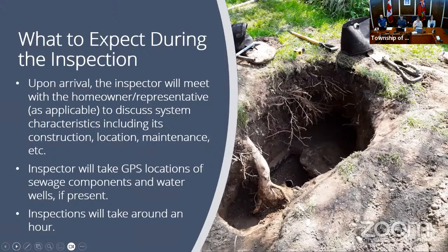We would also ask questions like maintenance. So when was that last pump out? Do you have that receipt? And then what is your typical pump out frequency? So just for us to know that you pumped it out 6 months ago doesn't necessarily help us or help you in our conversations to know if you're at an appropriate frequency, because we don't know if it's been 2 years or 20 years prior to that pump out.